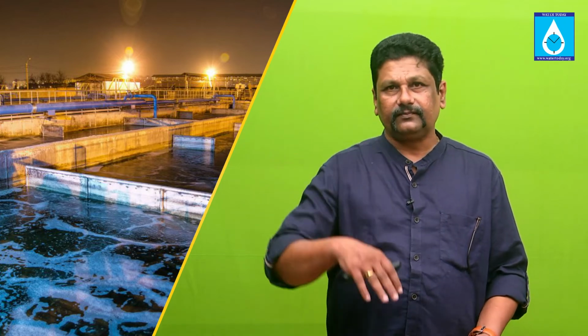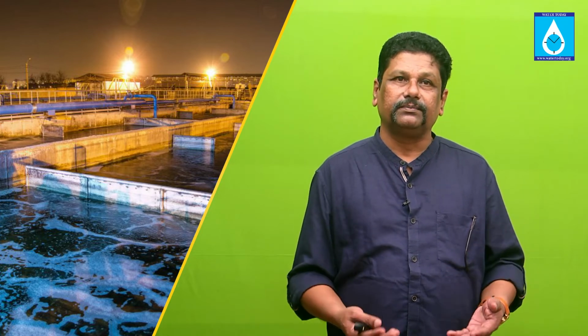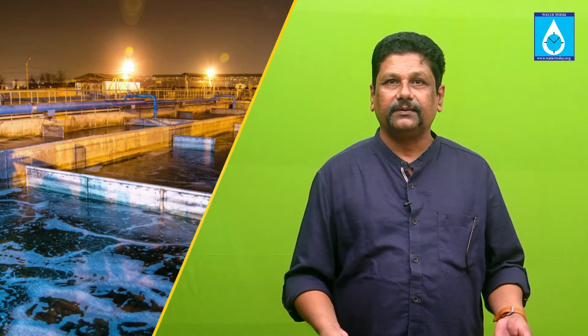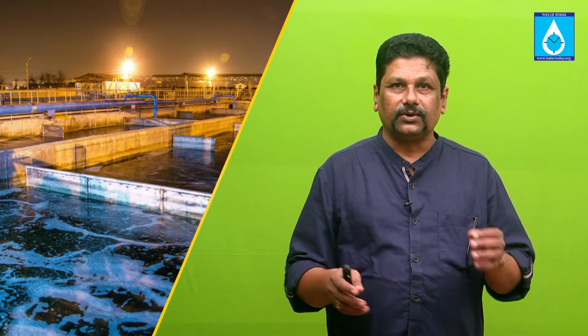and never put the pump very high, like you take it 1 meter above. And I have seen people doing this, taking it above, saying that there will be sludge accumulation, so the pump is not going to get immersed into it, so we put it 1 meter up. Again, you are killing the pump. So never put it like that, because your sewage pump is there to handle all that sludge. And if you start handling right from the beginning, you are not going to have sludge. But if you put it on the top, all that sludge will be there, which is not a good design at all.